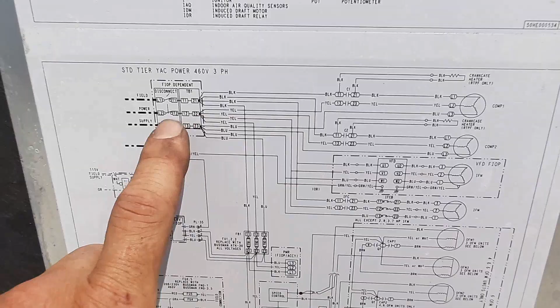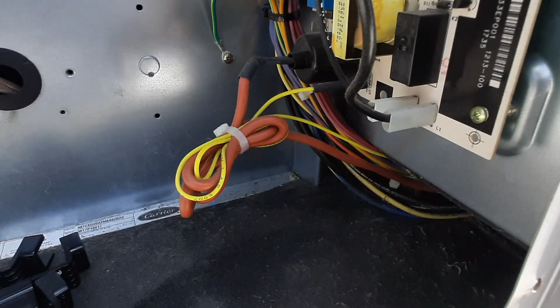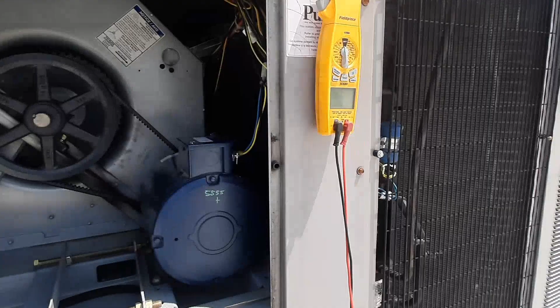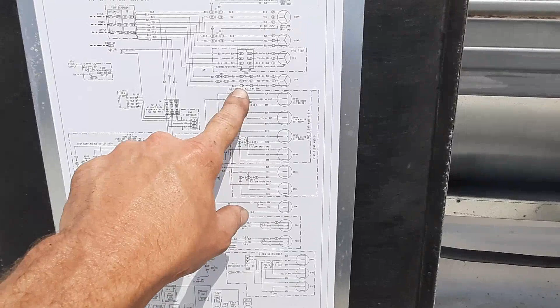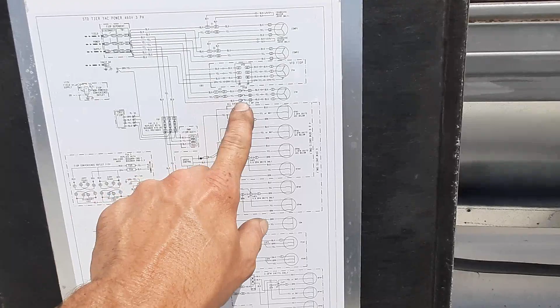My condenser fan feeds the transformer. You can get some rub outs up under here too. There's insulation, and I don't see or feel anything. I'm not getting a direct short, so we might try to isolate each motor and ohm it out. It shouldn't be the blower. The blower fan is fed from the indoor fan contactor as well, and that circuit breaker there. So if we had a blower problem, we would have tripped this. If we had a crankcase heater or any other problem, we would have blown a disconnect fuse or something.